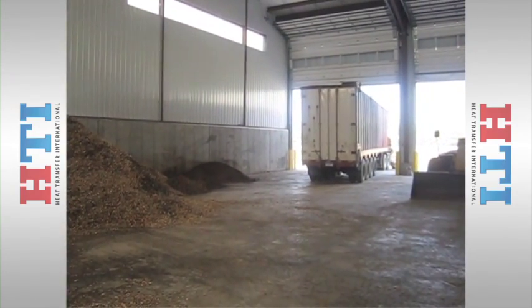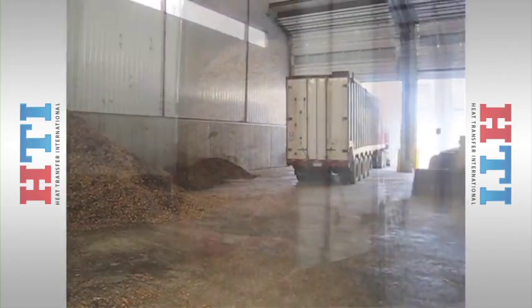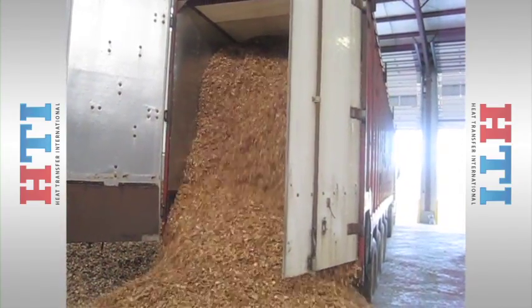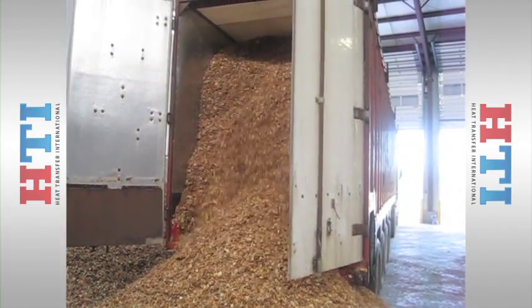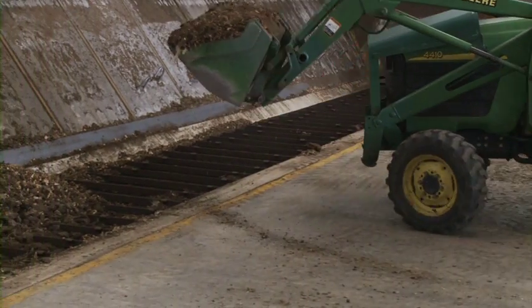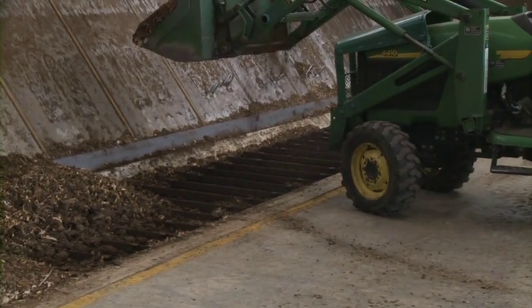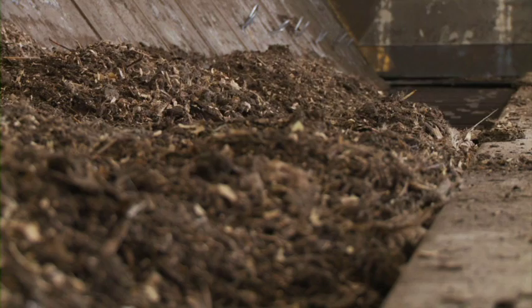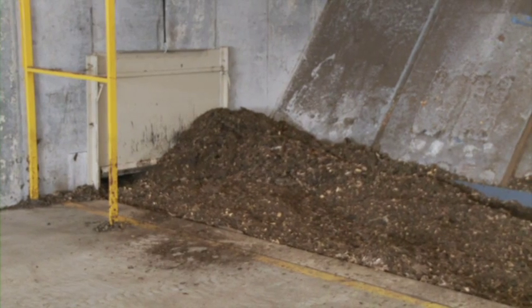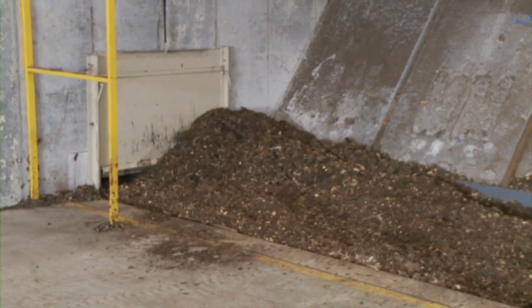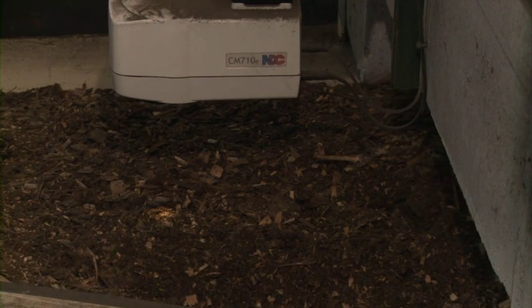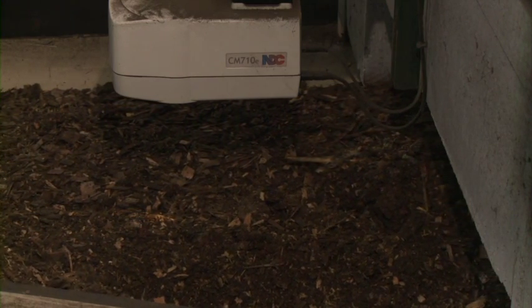HTI systems are compatible with over 50 different types of fuels. Turkey litter and wood chips are alternately used at this facility. The material is transferred to a series of conveyors that will move the waste to the gasifier. The material moves under a knife gate which levels the material for the optical moisture sensor. The moisture content of the material is recorded to the digital system controls through this optical sensor.